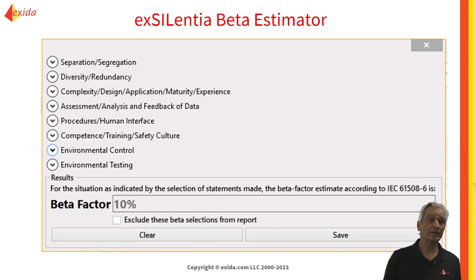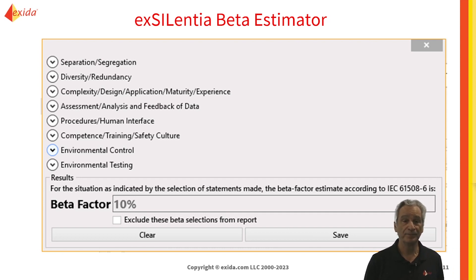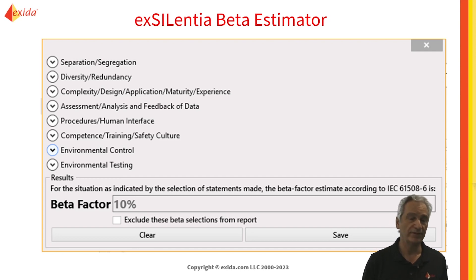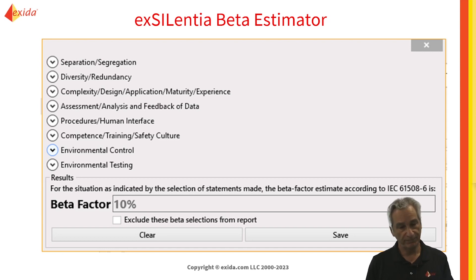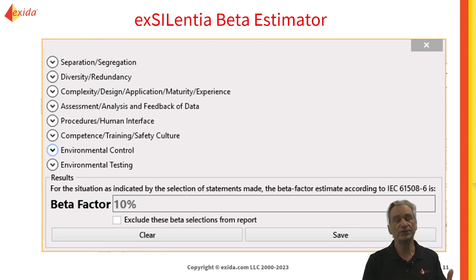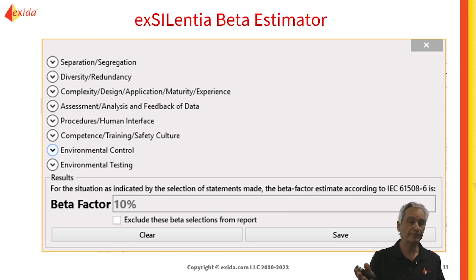exSILentia automatically, if you put in a redundant configuration, will pop up with the beta factor set to 10%. Within the headings we can check boxes to say yes, we're using diversification; yes, we've got separate systems in separate boxes; and there are systematic aspects such as whether the maintenance people are properly trained and regularly trained. If we check all the boxes, we can get down to 2 percent. But again, that reduction down to 2 percent and the improvement in the PFD average — does it offset the additional cost incurred elsewhere? That's the thing with the life cycle: we can balance it out and make informed decisions.